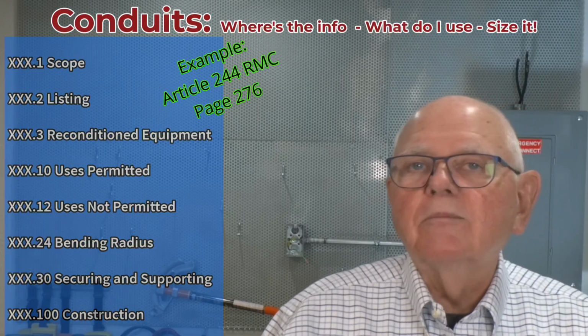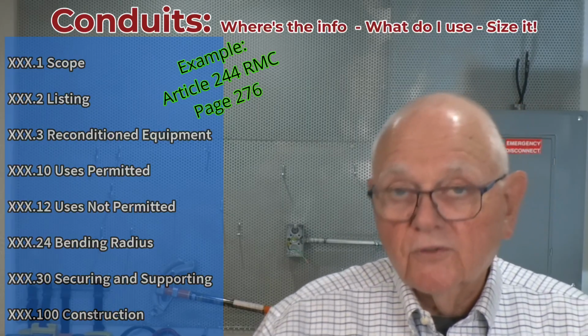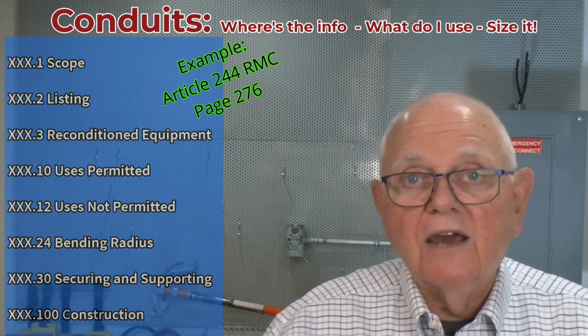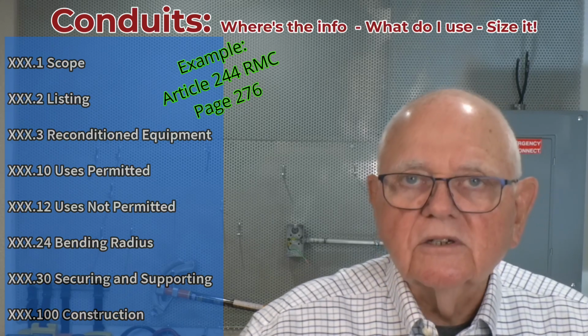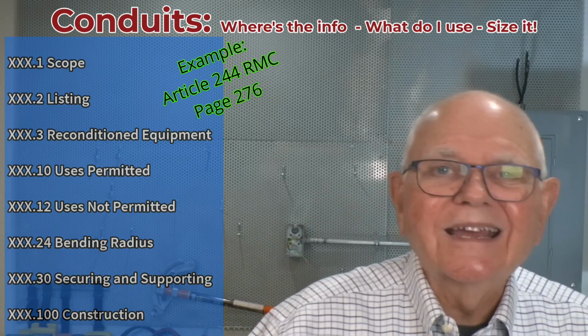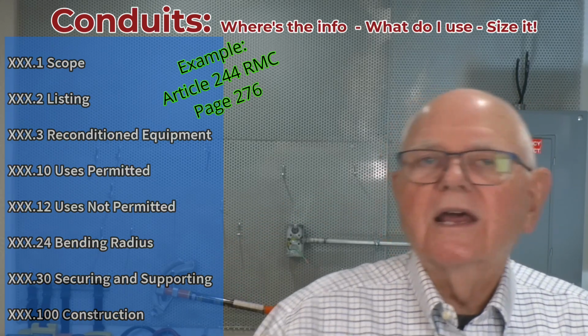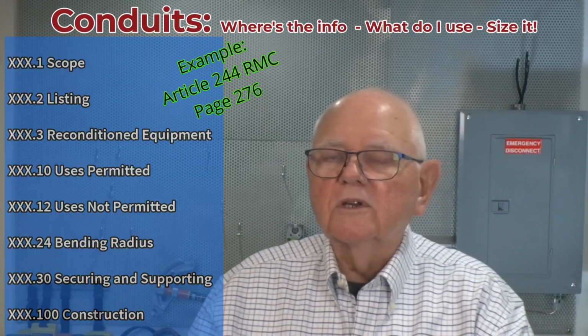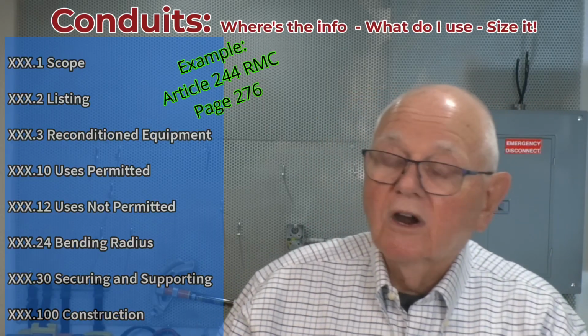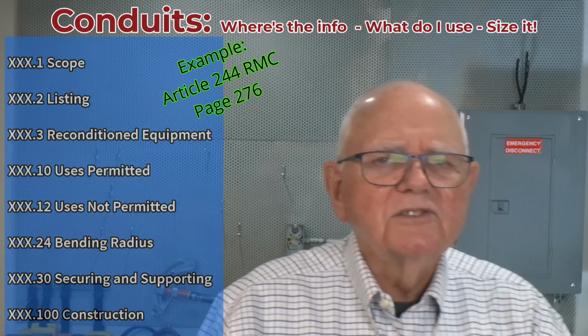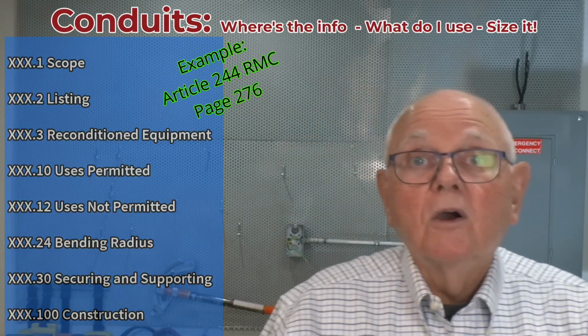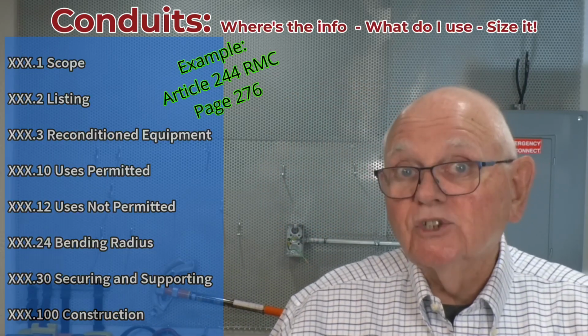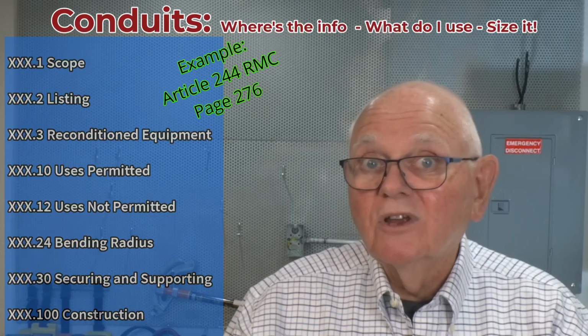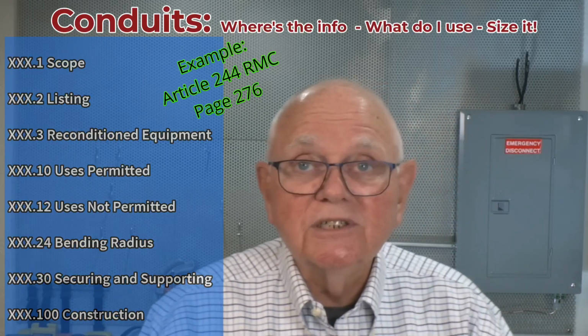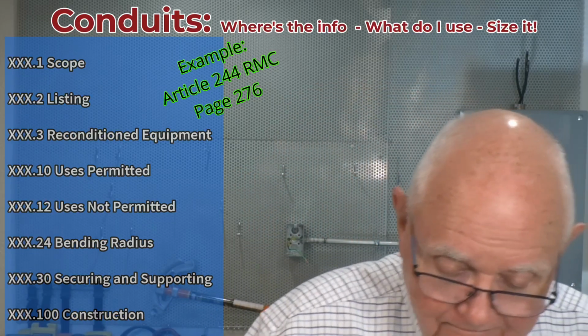344.24 talks about my bends. No more than 360 degrees in the run without putting some type of box or conduit body or something where I can access those conductors. That's one I don't want to violate anyway, right, when we pull conductors. It's just getting too hard to try and pull conductors. And it tells us that not only is it going to be hard, but what? It says you don't want to damage your conductors, certainly, by having to pull on them too hard and damage the insulation, damage the conductor.